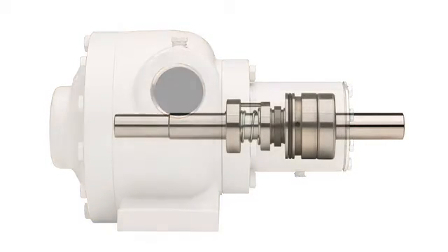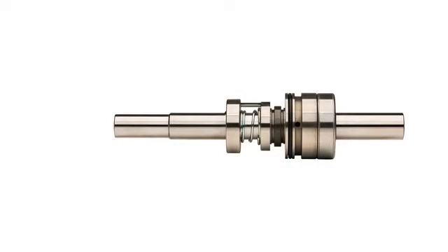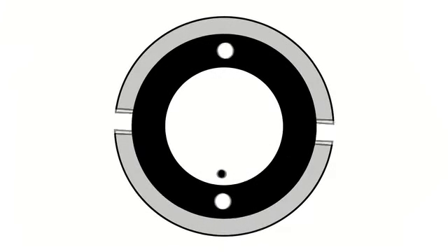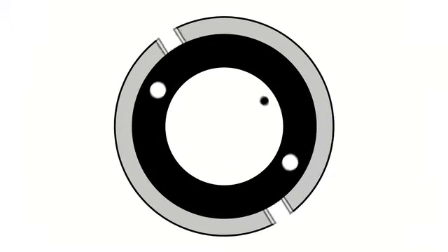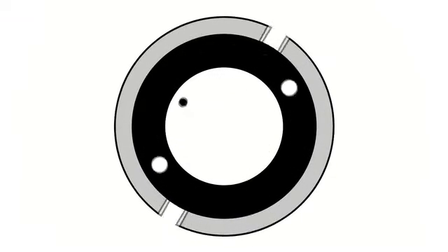The design used today incorporates three pieces: two metallic seals and one intermediary seal. This minimizes friction-associated wear due to high drive speeds, because the intermediary seal actually rotates at one-half the pump drive shaft speed.